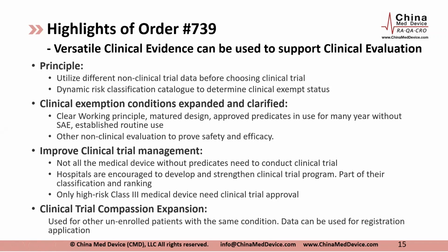So the clinical exempt conditions are expanded and clarified. And I'll talk more about this principle. If the product is pretty clear, it's matured, the working mechanism is clear, and there are no post-market AEs, you may not need a clinical evaluation anymore. You clearly don't need it as much. And for clinical trial improvement, that's also spelled out. There's a subsequent regulation to support it and how to make that process more streamlined.